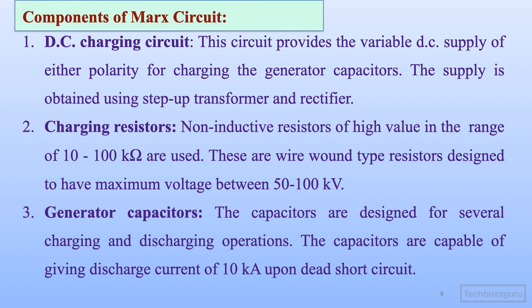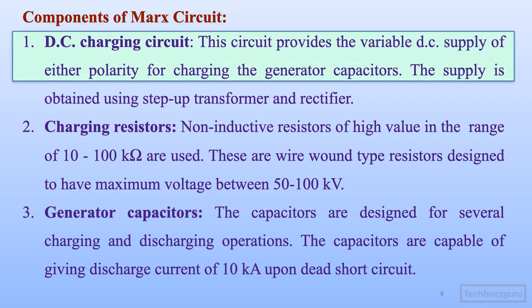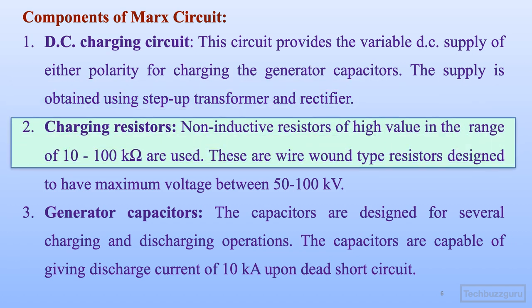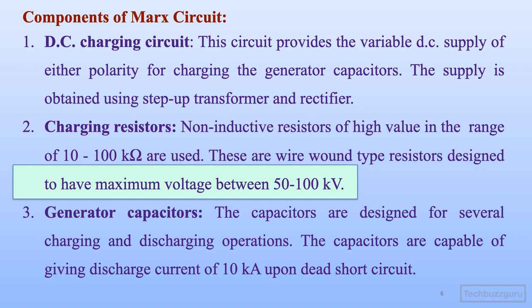Let us move ahead and check the circuit construction and various components of the Marx circuit. The first and foremost is the DC charging circuit, which is required to provide a variable DC supply of either polarity for charging the generator capacitors. The supply is obtained using a step-up transformer and a rectifier. The second element are the charging resistors — these are non-inductive resistors of high value lying in the range of 10 to 100 kilo-ohms, wire wound type, and designed to have a maximum voltage drop of 50 to 100 kV across them.